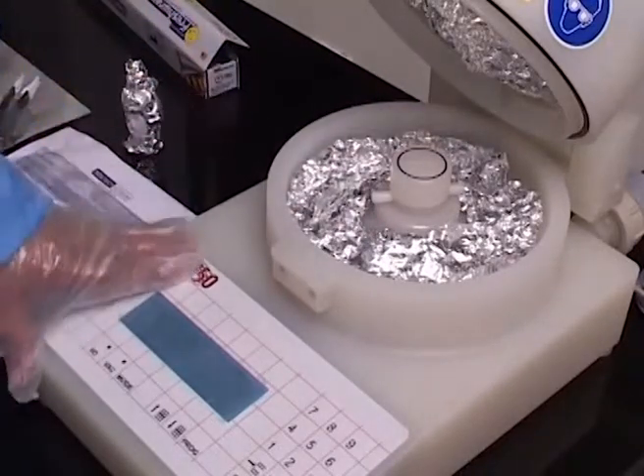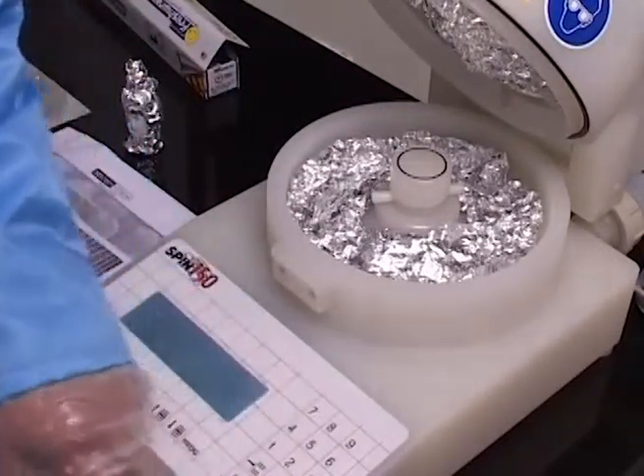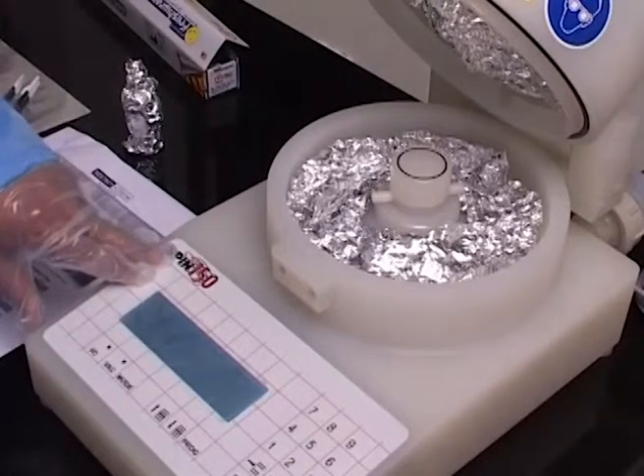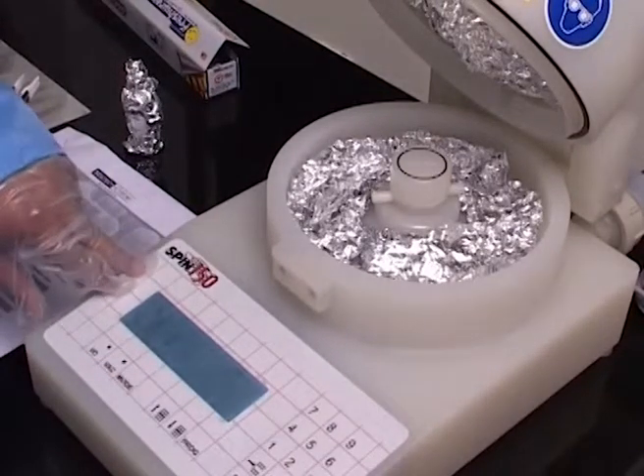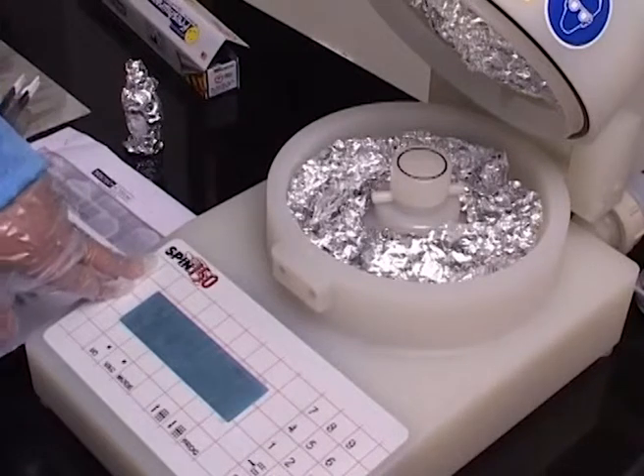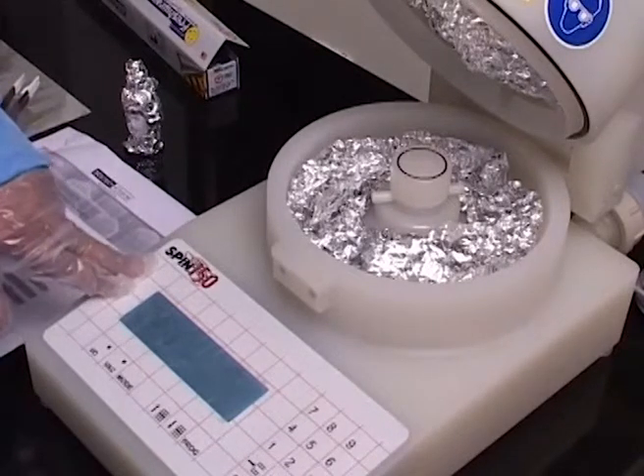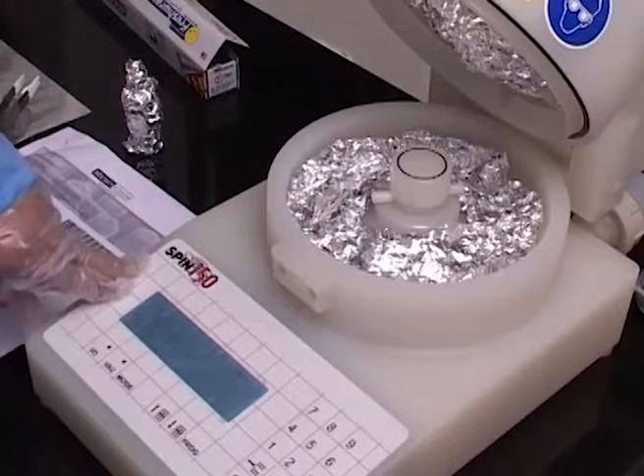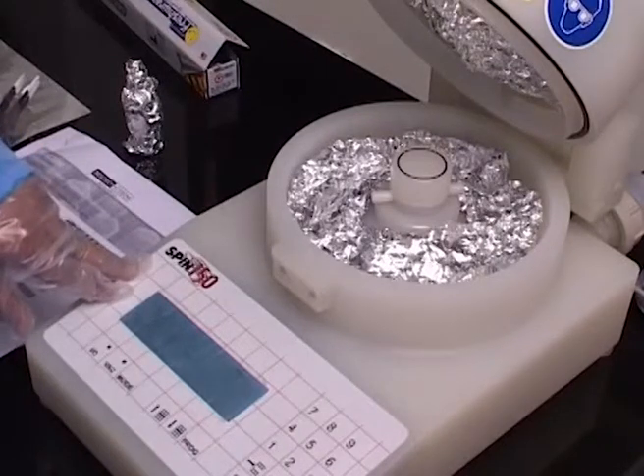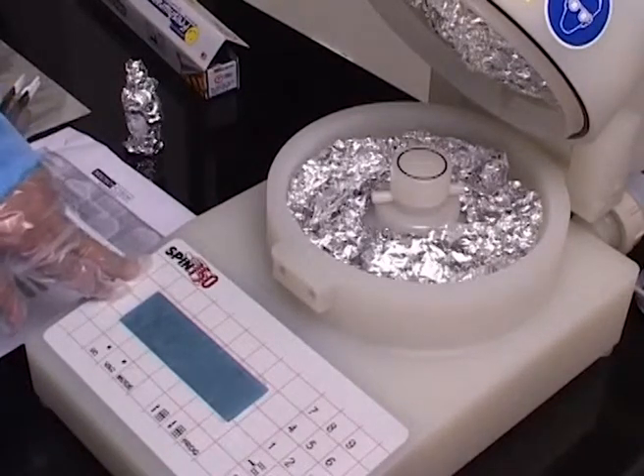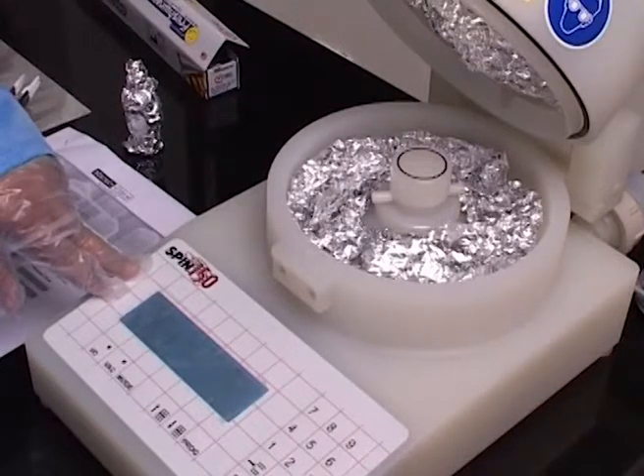What is also important for me to tell you is that there is a control here which we can use for flexibly controlling the spin speed, the amount of time for which we hold at a certain speed, and also, very critical for different grades of resist, the acceleration at which you rotate in order to achieve a certain speed.